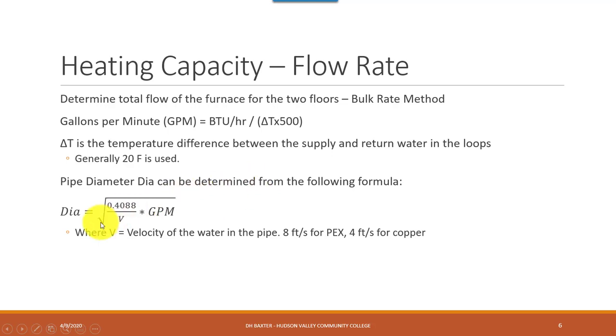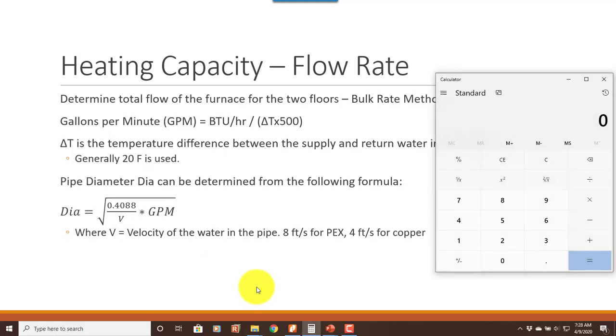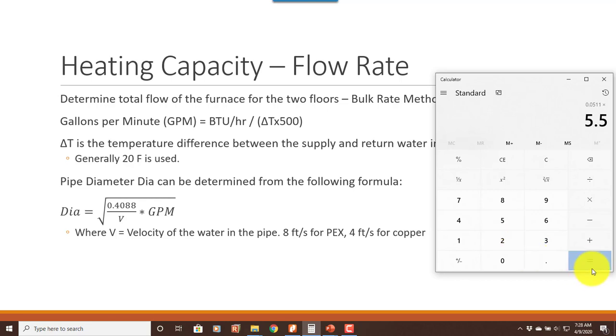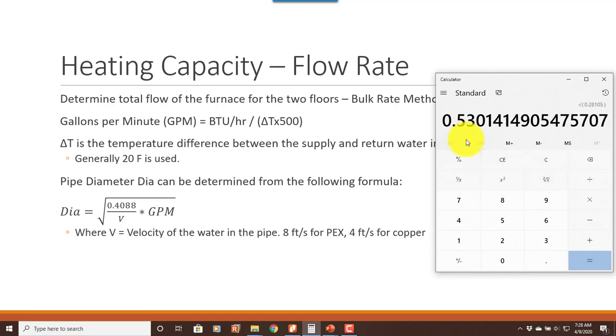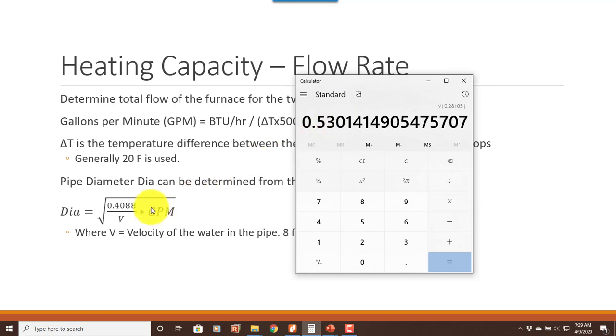Now the pipe diameter can be found if you really want to calculate it. It's the square root of 0.4088 — that's a correction factor — divided by the velocity of the water in the pipe, which for PEX is 8 feet per second, times the GPM. So on the calculator: 0.4088 divided by 8 feet per second equals 0.0511, times our 5.5 gallons per minute, then take the square root — and we get 0.530, or half an inch.